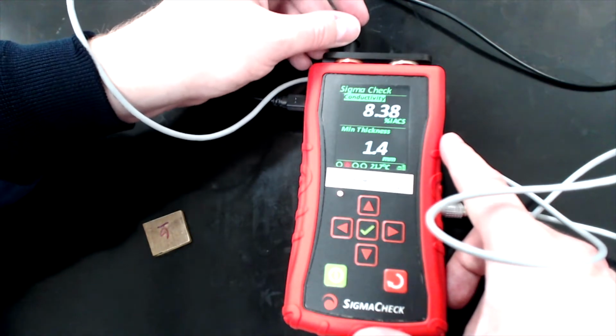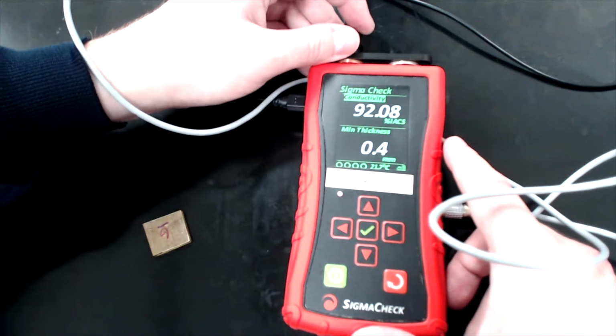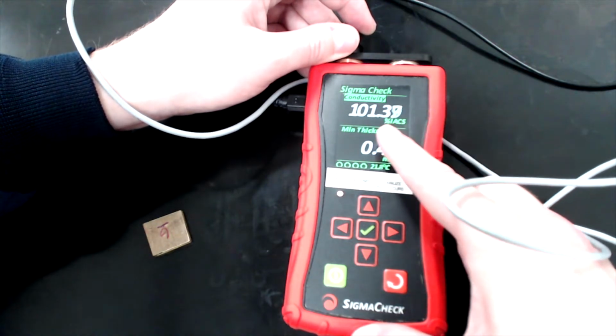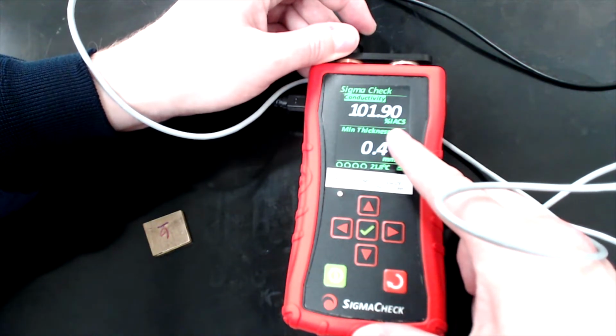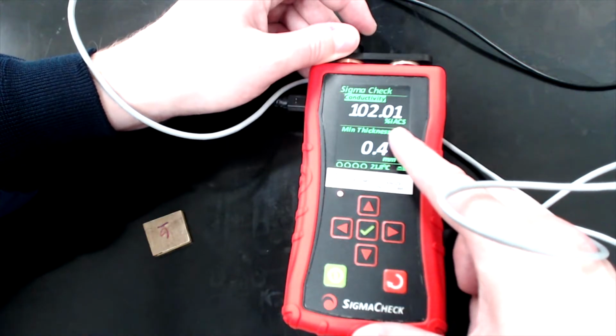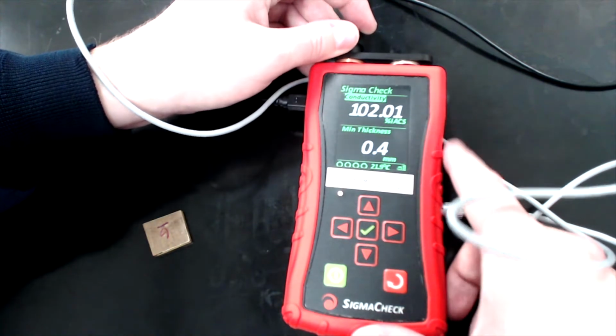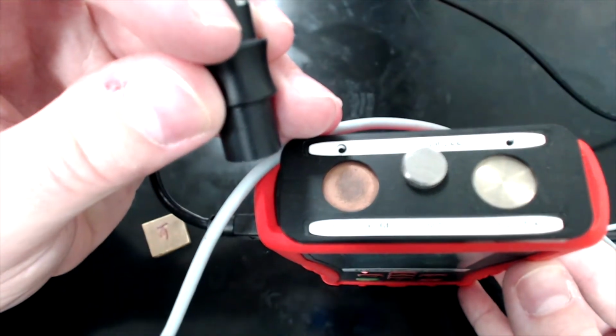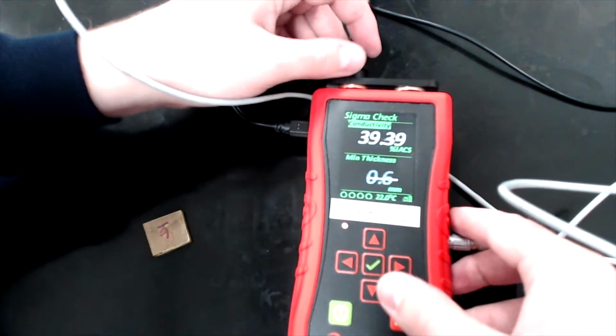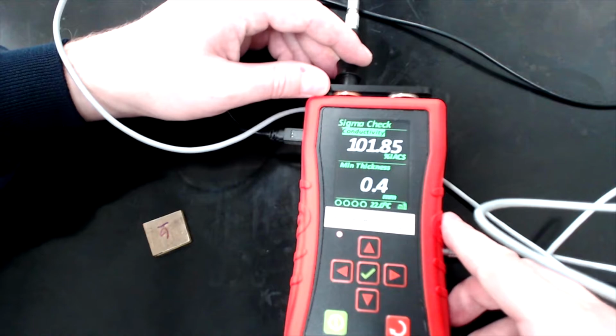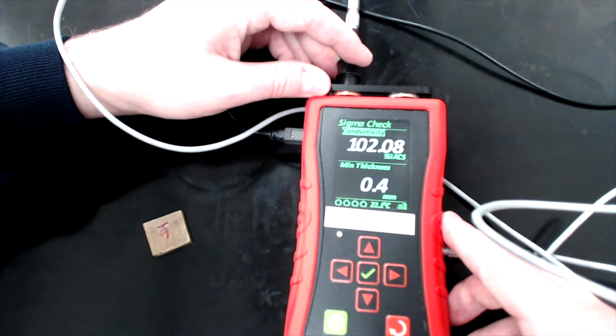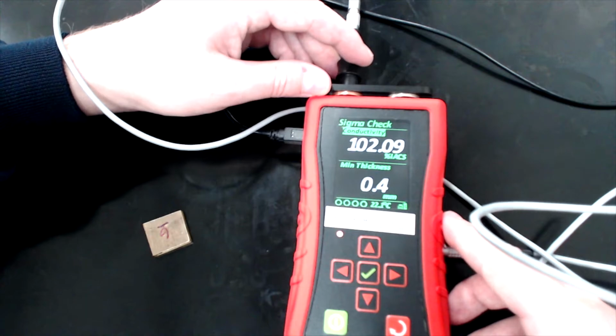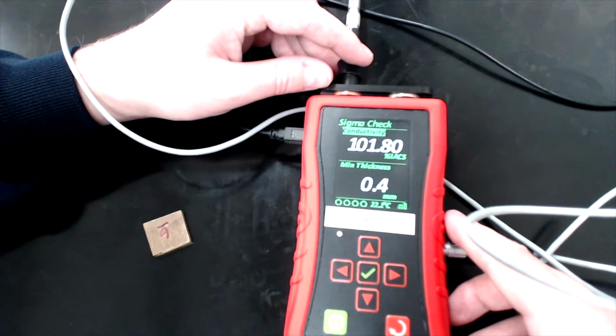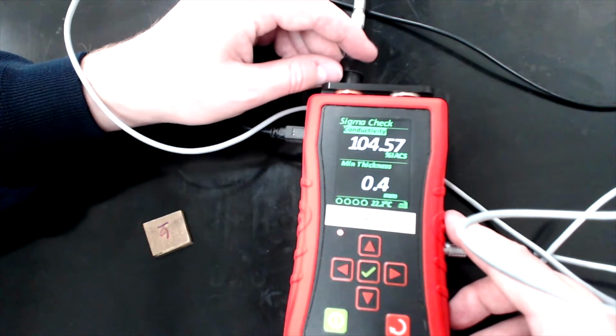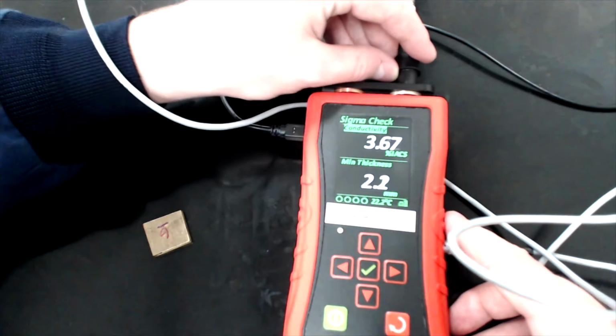You can also go back and now that it's calibrated, put the probe on the standard and check it and see how close it is. So this one says 102.01. It should be 100.68. Let me check that again. Should be 100.68. So it's 1 or 2 points off. I'll do it again just to see where it's at. 102 again. And so this tells us that it might be drifting a bit. And so one thing we can do is check the calibration again, or we can check the other one to see where we're at.